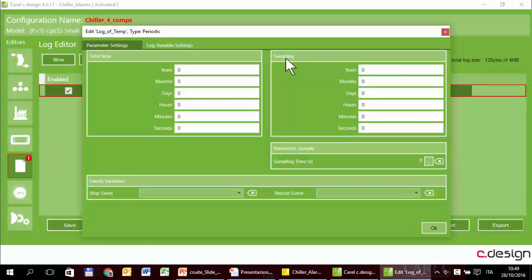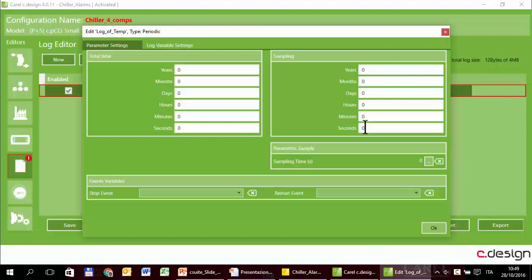We can start with the sample time, so the variable will be logged every this time. In a real application this time is about 5 to 10 minutes, but in this exercise, just to have some samples in a short time, we can set 5 seconds. Then total time, one week, that is 7 days.